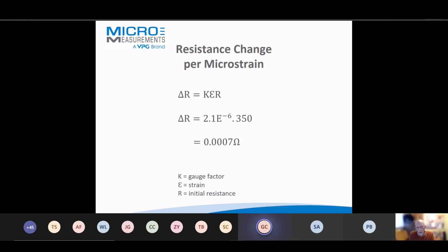So the first thing is a simple formula, a rearrangement of the gauge factor formula. We have our change of resistance, which equals the gauge factor times the strain times the start resistance. Gauge factor normally around 2, for 1 microstrain or 0.000001, times 350. So we have a change per microstrain, in this case, of 0.7 of a milliohm.